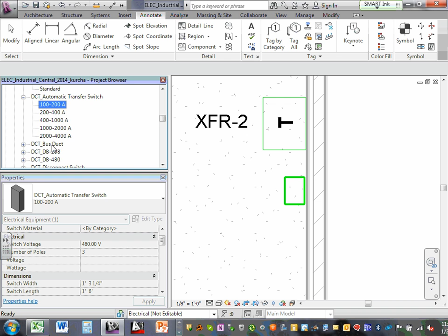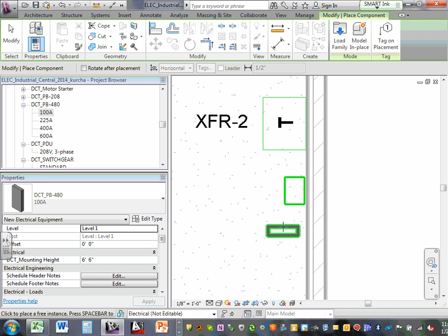Okay, let's go grab a panel that goes with it, guys. It's a 280, it's going to be a lighting load, so it's going to be 480. Here's my 480, smallest we're going to get is 100 amp. So drag that 100 amp panel and put it right next to the transformer.